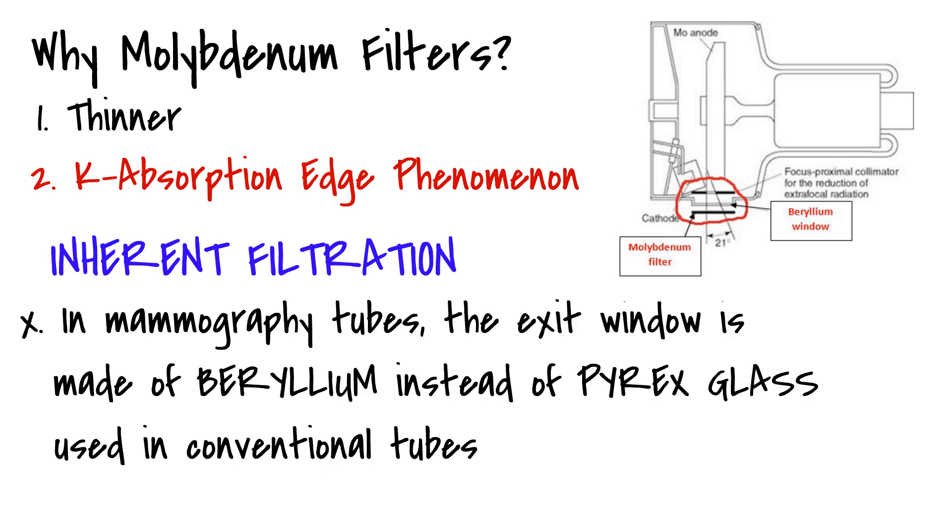Like you may have guessed, pyrex glass is too thick to allow the low-energy mammography photons to pass through. So, the exit window of a mammography tube is commonly made of beryllium instead.